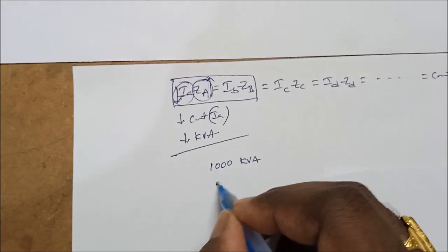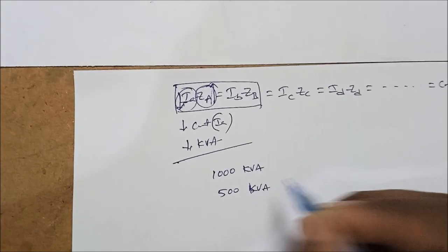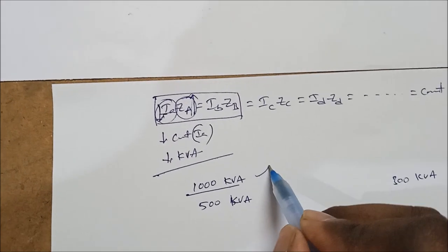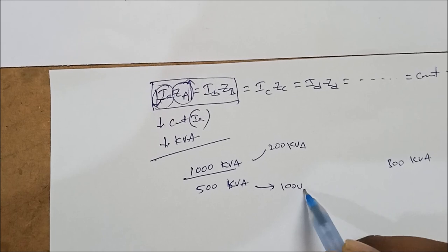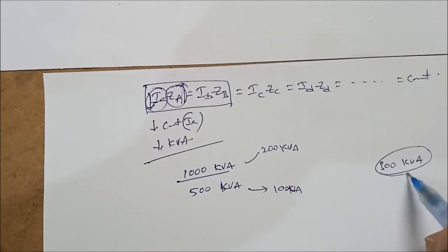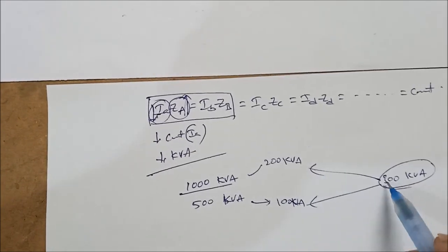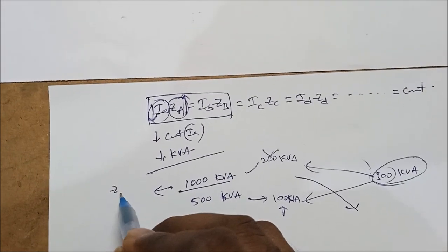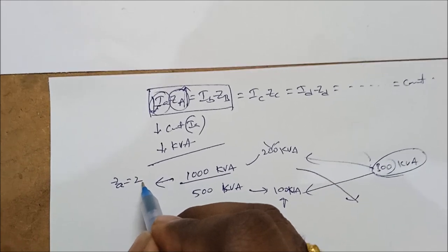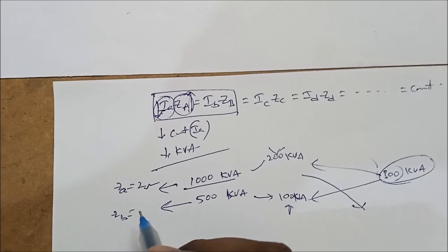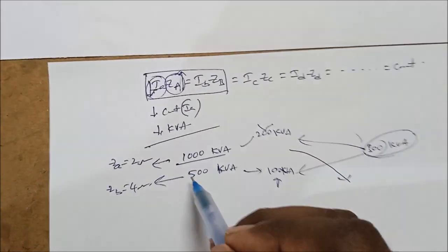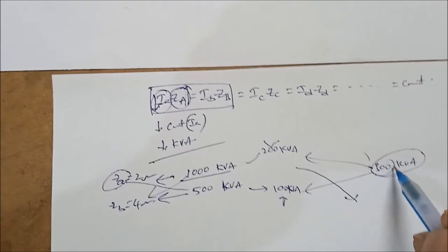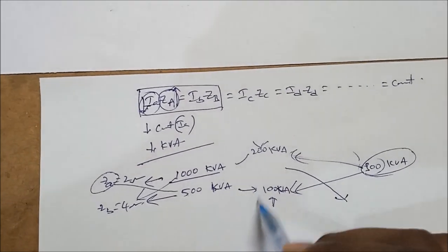For example, if the first transformer is 1000 kVA and the second is 500 kVA, with a total load of 300 kVA, the first shares 200 kVA and the second shares 100 kVA — in proportion to their kVA ratings. If the impedance of the first transformer is 2 ohms, then the impedance of the second should be 4 ohms, since impedance is inversely proportional to kVA rating.